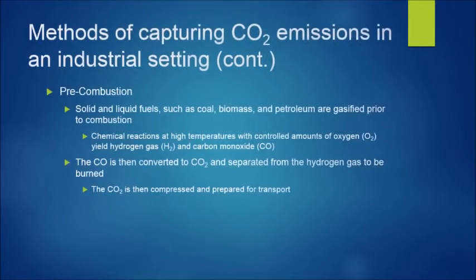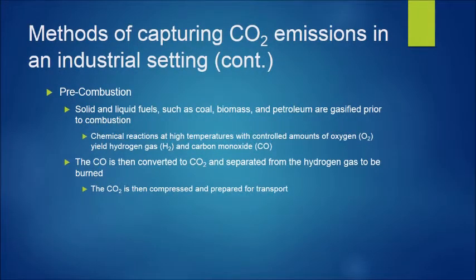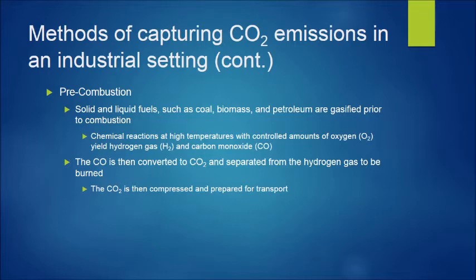Pre-combustion carbon capture can be applied to any solid or liquid fuel source, such as coal or petroleum products. The fuel is first gasified. If it is a solid fuel source such as coal, it gets pulverized into a fine particulate dust; if it is a liquid such as oil, it simply gets atomized. The now gasified fuel gets heated to extreme temperatures, reacting with controlled amounts of oxygen, or O2, yielding hydrogen gas, H2, and carbon monoxide, CO. The carbon monoxide is then separated and further reacted to create carbon dioxide, which is then compressed into a liquid and prepared for transportation. The hydrogen gas is then used as a fuel source, burning cleanly with oxygen, creating only water as a byproduct.